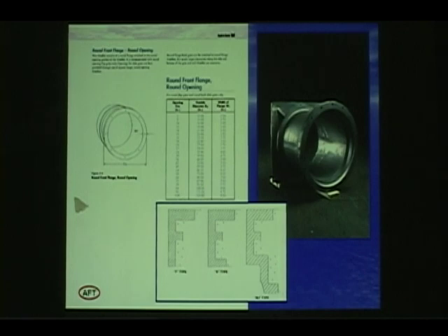You have an F-section thimble, you have an E-section thimble, or you have a mechanical joint thimble, simply used on the right application. Most thimbles are the F-section. You would use an MJ, mechanical joint connection, for one where you're connecting into a piece of pipe.